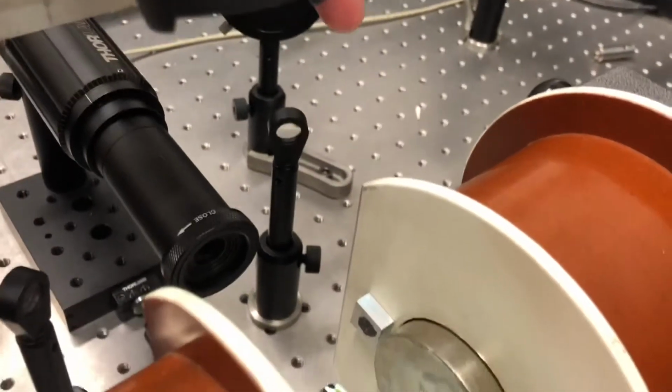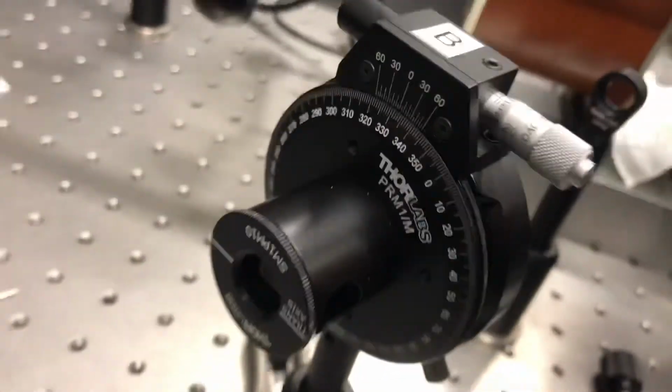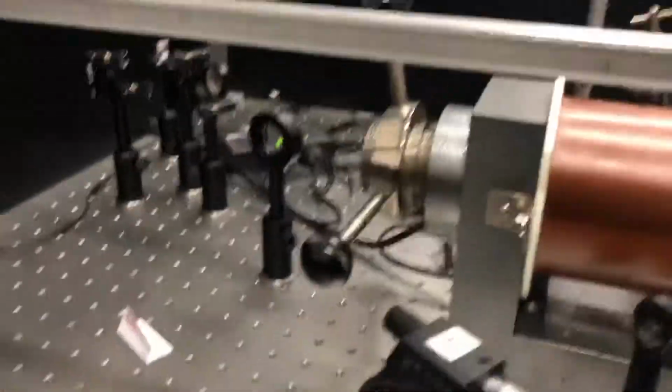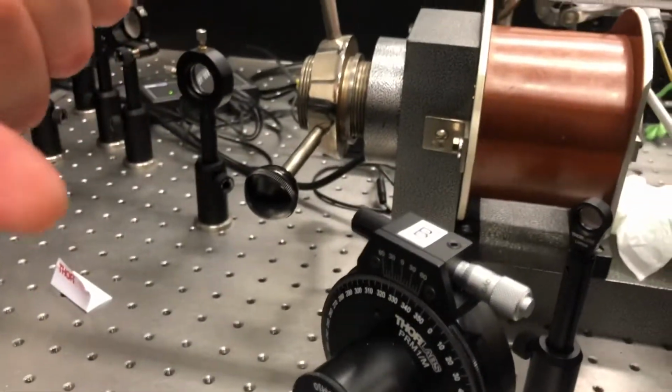Now the laser is then reflected off that sample and it passes through these lenses here all the way through, and then it is bounced to this detector. But here we have another polarizer which is orientated orthogonally to the first polarizer, so it only allows light through that is polarized left to right.